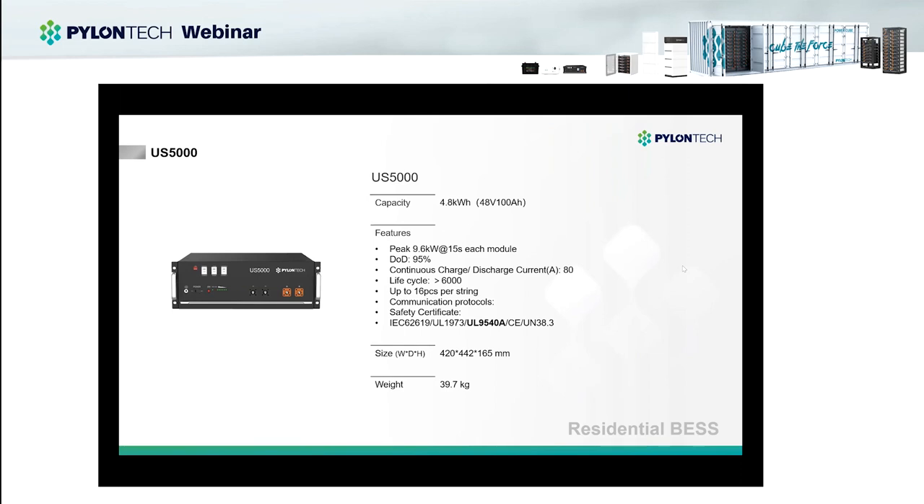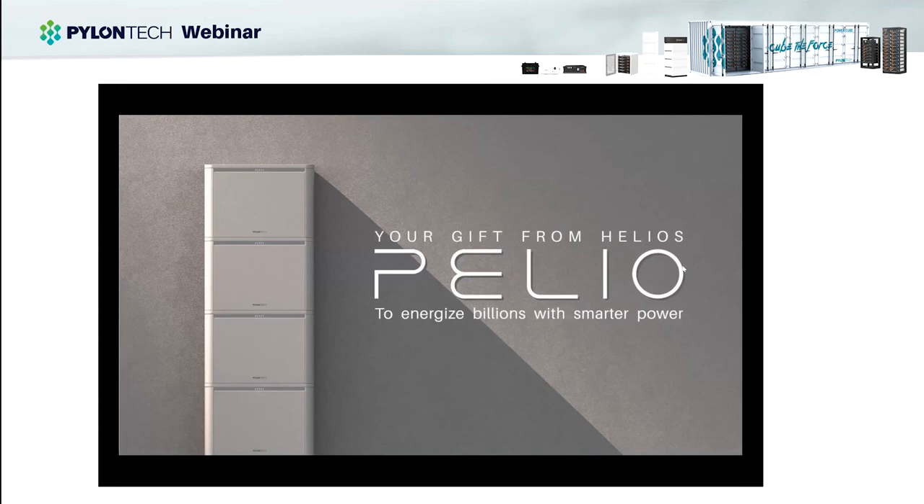The US5000 has similar features to the US3000C but is bigger — 4.8kWh, 48 volts, 100Ah. It also supports peak 9.6kW for 15 seconds. The continuous charge and discharge current is 0.8C, meaning it can support continuous discharging at 80 amps. We have all the certifications needed to sell these products around the world — IEC and UL, especially UL9540A — so we can also use these batteries in the US market. This is our new Pelio product released several months ago. You can see it has a stackable design with a smaller floor footprint and strong high power performance — it can operate up to 1C.